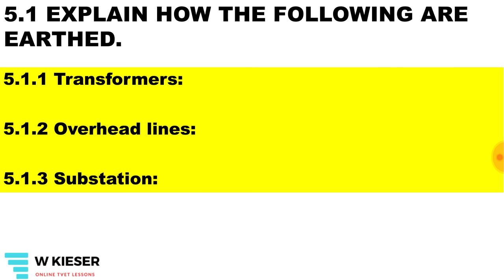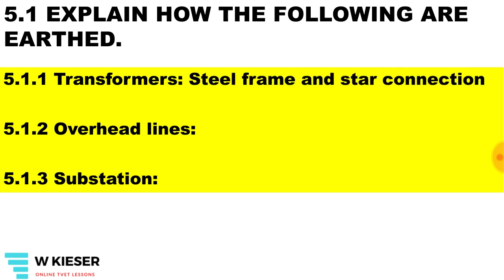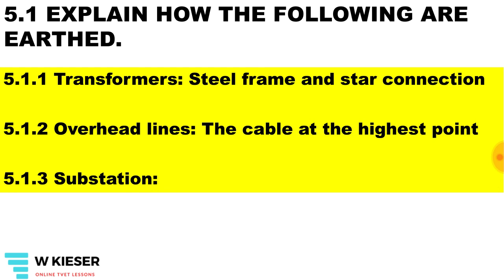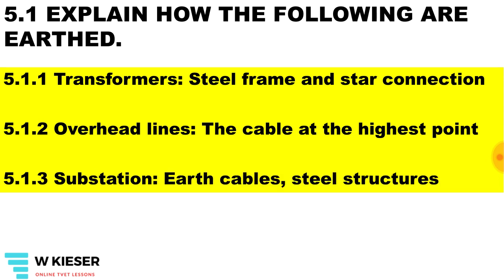Explain how the following are earthed. For transformers, the steel frame and the star connection on the star winding is earthed. For overhead lines, the cable at the highest point is earthed as well as the pylons connected to ground. For the substation, the earth continuity conductor is connected to ground and any steel structure is also connected to earth.